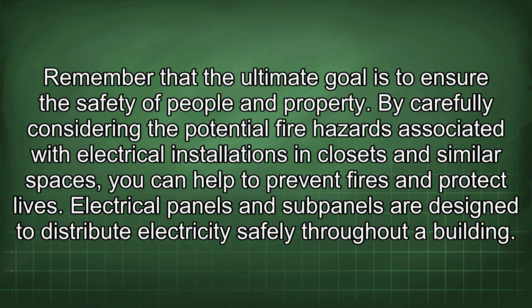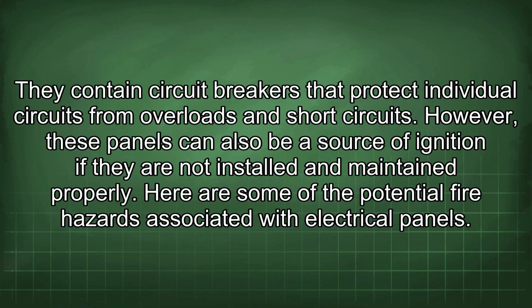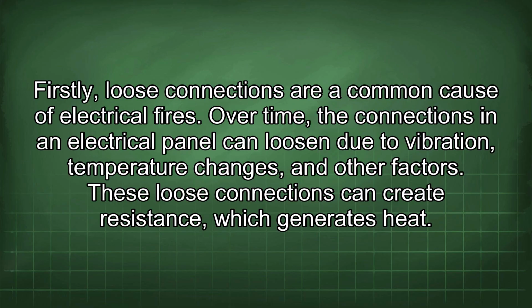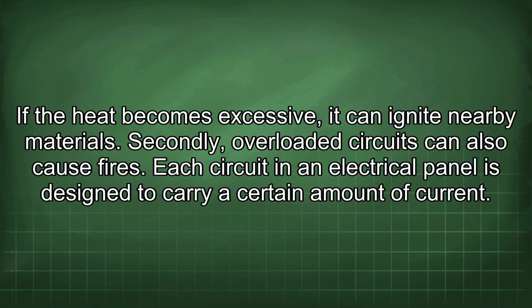Electrical panels and subpanels are designed to distribute electricity safely throughout a building. They contain circuit breakers that protect individual circuits from overloads and short circuits. However, these panels can also be a source of ignition if they are not installed and maintained properly. Here are some of the potential fire hazards associated with electrical panels. Firstly, loose connections are a common cause of electrical fires. Over time, the connections in an electrical panel can loosen due to vibration, temperature changes, and other factors. These loose connections can create resistance, which generates heat. If the heat becomes excessive, it can ignite nearby materials.